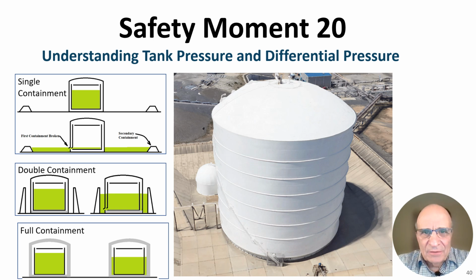Safety moment number 20. I'm going to talk about understanding tank pressure and differential pressure. All gauges are differential pressure gauges. We don't commonly think of it that way because we commonly think if you get a pressure gauge that reads 0, you put it on a pipe and it reads 20 psi, that it's reading the pressure that's in the vessel or the pipe that you're measuring. Well, actually, it's giving you a pressure differential between the pressure in the pipe and the pressure measured by a barometer. It's measuring with the 0 point calibrated to be 1 atmosphere.